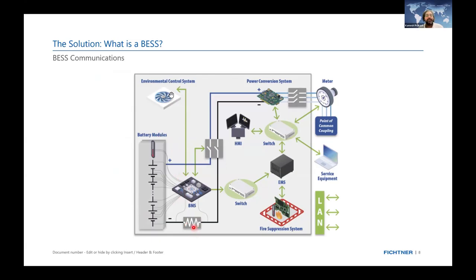This is a pre-charging resistor, and then we have the BESS batteries in series or parallel combinations, along with the BMS—the ECS handles this part. We have a main isolator or switch to connect and disconnect, and the PCS, either DC-DC or DC-AC bidirectional, connecting to the grid. The fire suppression system works in parallel, all connected via fiber optic cables. The challenging part is how it all communicates: at the system level, batteries communicate with the BMS, which communicates with the network switch, and then to the EMS.